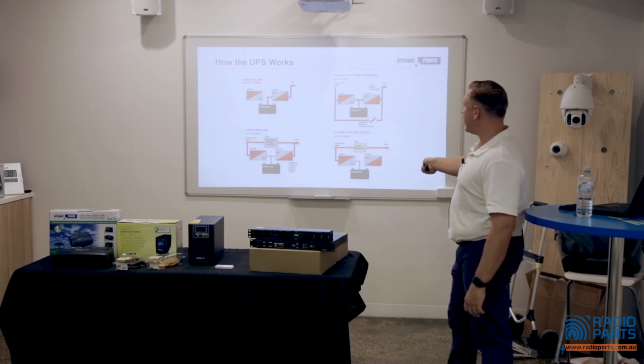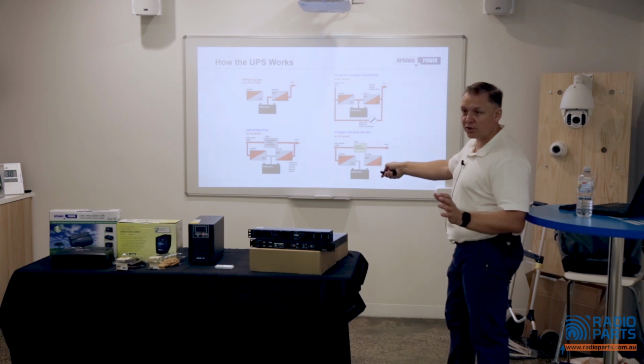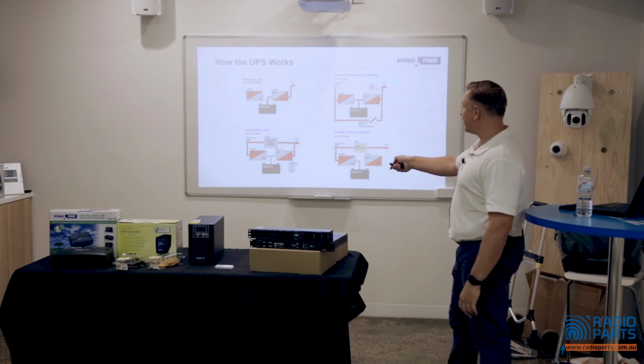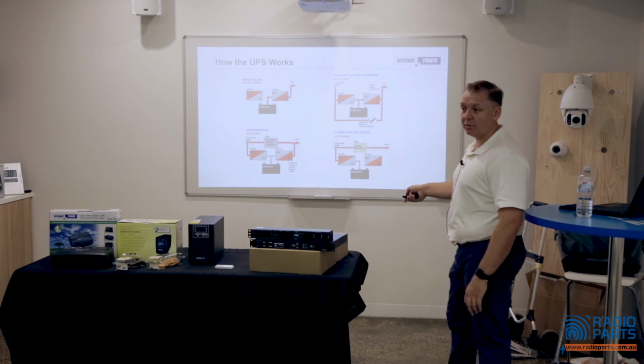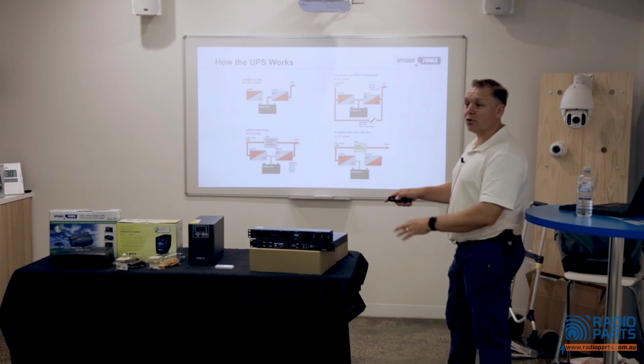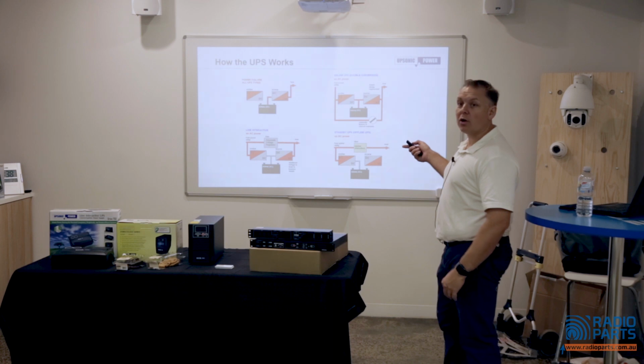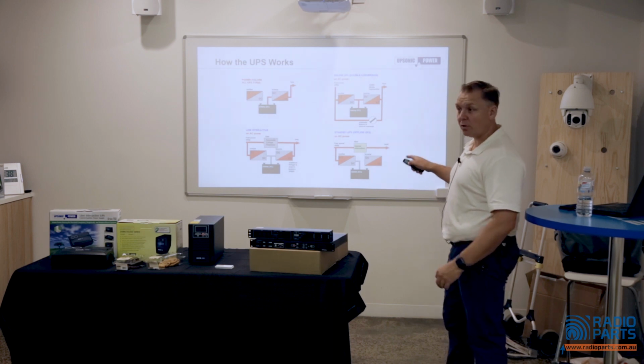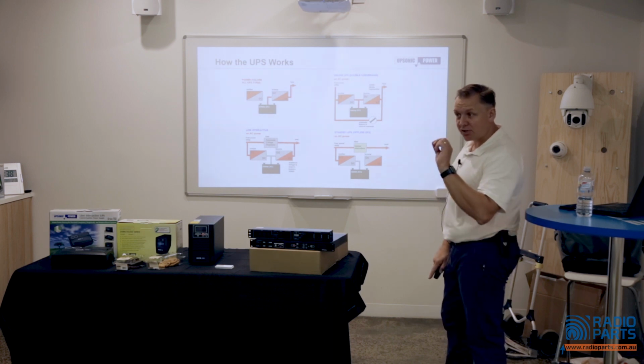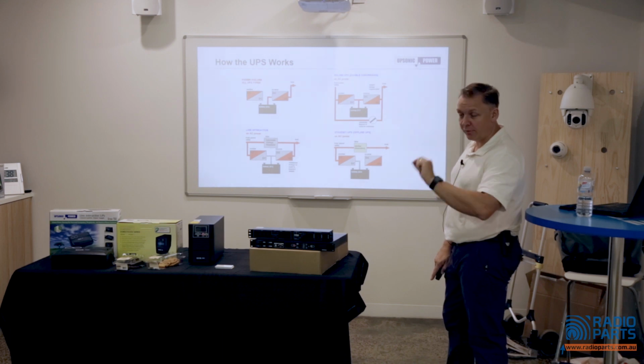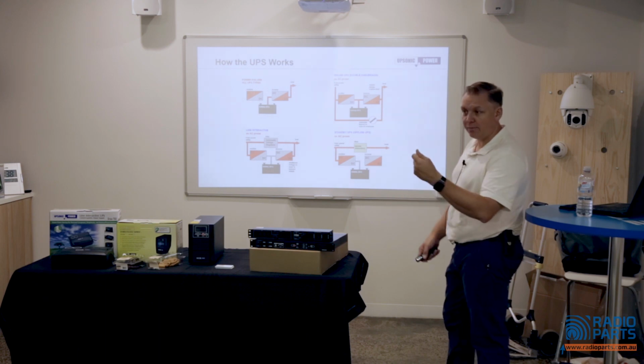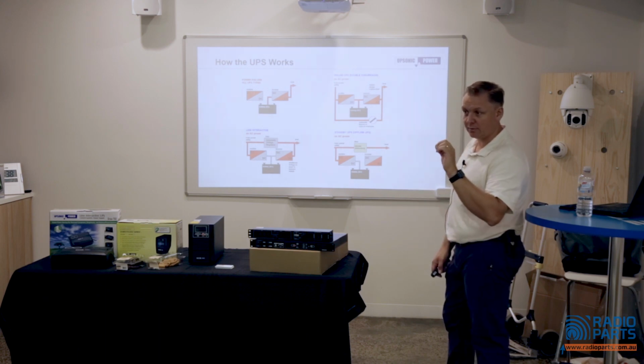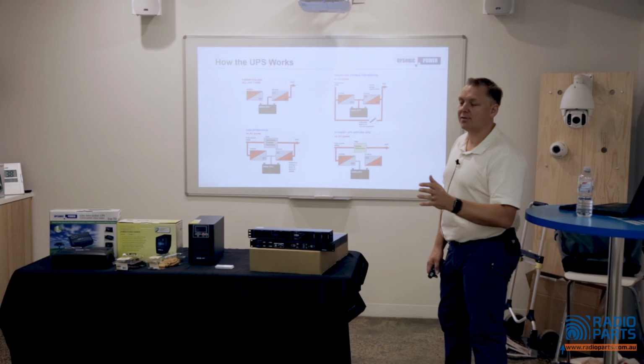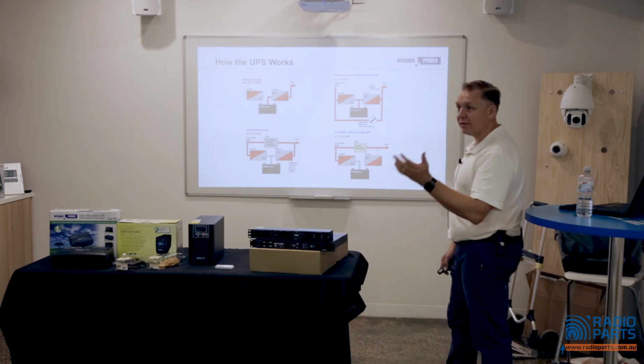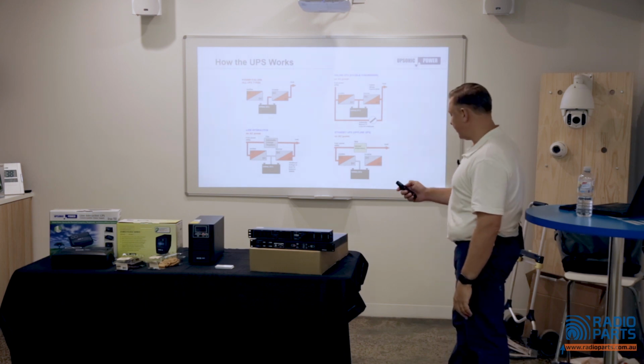With a line interactive or a standby unit, and a normal supply when the mains is running, your supply comes straight through the voltage regulator out to the load. The other stuff isn't doing anything. It's one of the reasons why when supply actually drops with a line interactive or standby, there's a tiny little break until the inverter starts running and the battery supply kicks in. If you connect up a light fitting to it, you can see the light just flicker for a second. Most PCs and things, that's fine. Even a TV won't flicker on a modern telly.